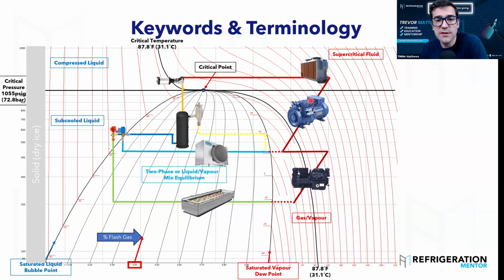I have conversations like, well, what causes that compressor to work harder? Well, it's pressure ratio. That's it. The bigger the pressure ratio, the more work that compressor is going to do, the more heat that stator is going to produce. It's pressure ratio or compression ratio; depending on where you're at in the world, you'll call it differently. But as that pressure ratio increases, it's just more work for those compressors. More work leads to more energy. More energy leads to higher cost.